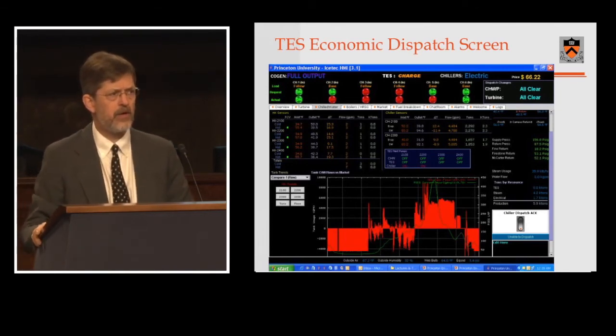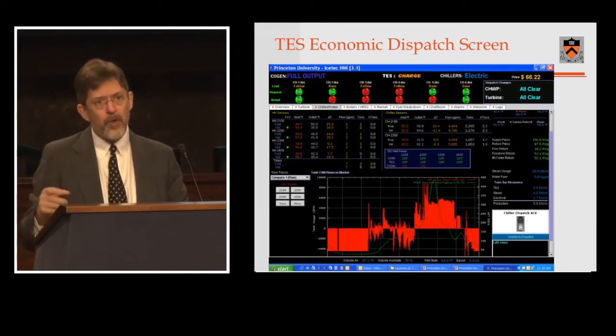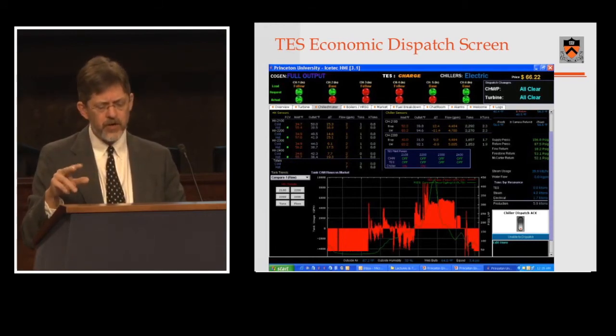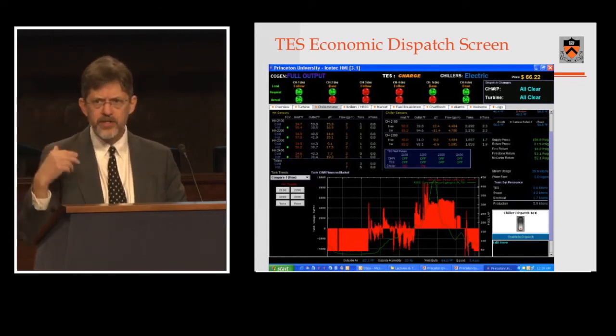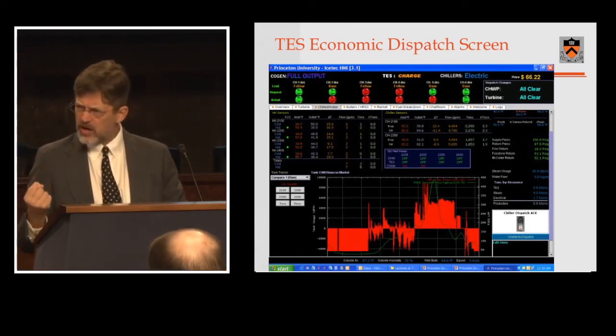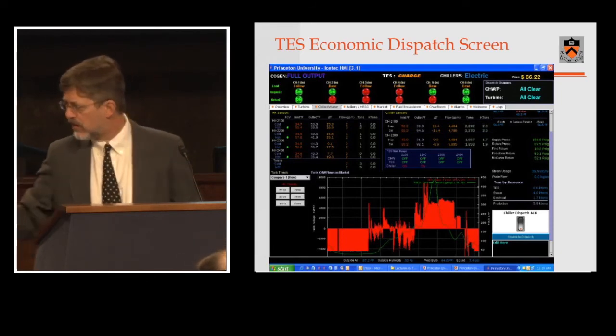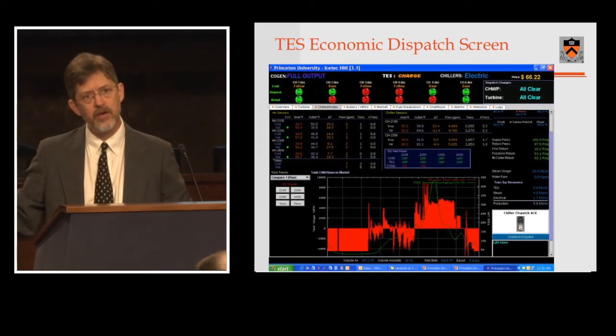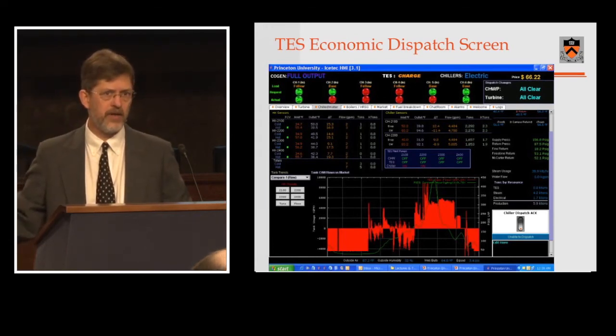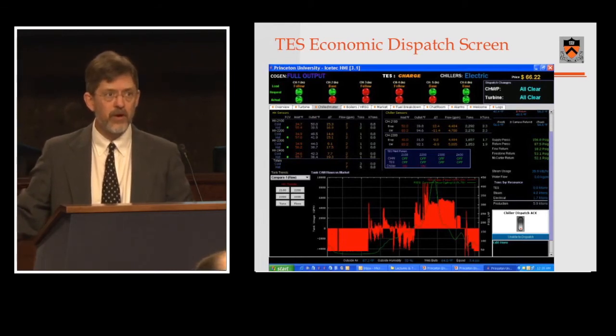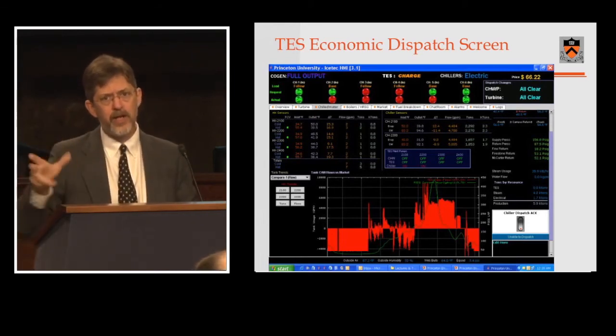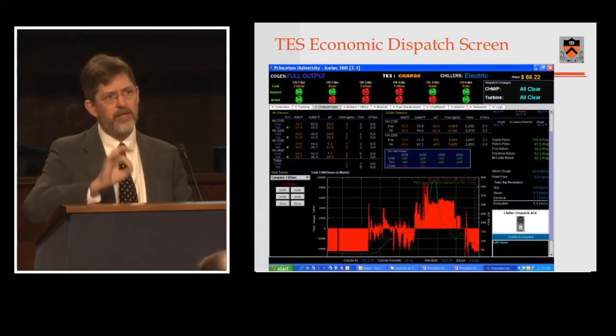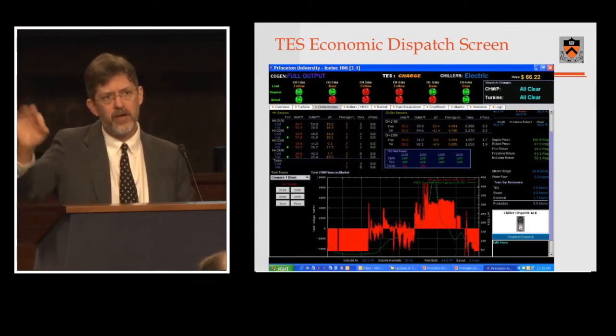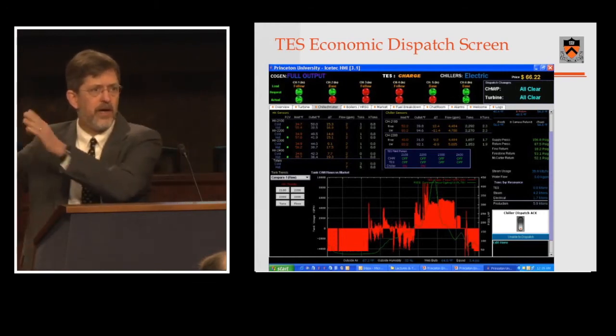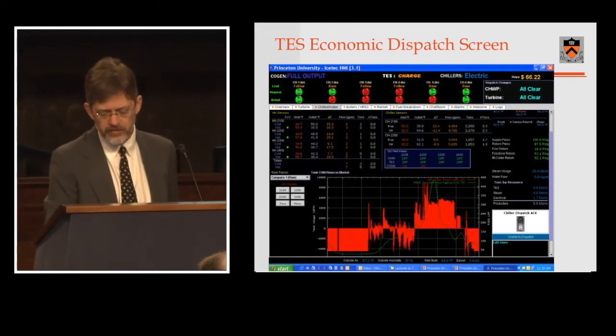The green is the price of power in that 24-hour period. While we were charging the tank, the price of power was maybe 25 bucks a megawatt hour. While we were discharging, the value of power was about $250 a megawatt hour. So I bought a commodity that cost me 25 bucks, and 12 hours later I delivered it to my customer when they would have had to pay $250 for that same commodity. That's pretty good ROI, pretty good leverage on my investment. We do that every day, 365 days a year. We predict the lowest price and deliver at the highest price, trying to span that low and that high with our power purchase and delivery.